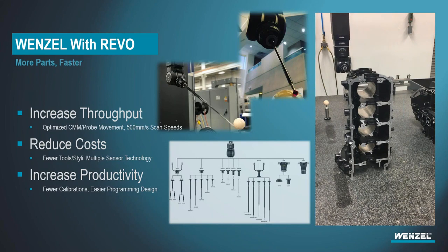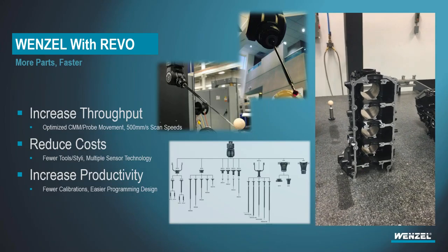Revo has a lot of tips and tricks that make this even more effective. As you can see here, the CMM is going to fix in place as we enter a hole, and you can see just the head spin to take the inspection points. We're picking up thousands of measuring points here in the cylinder bore, and you don't have to worry about the machine becoming stable, machine movement, machine settling, or anything like that. You take all of the physics of the bridge operation out, you fix that lightweight head in place, and then you can scan at speeds of up to 500 millimeters per second, making the Revo a highly efficient, very fast tool for your production environment inspection.